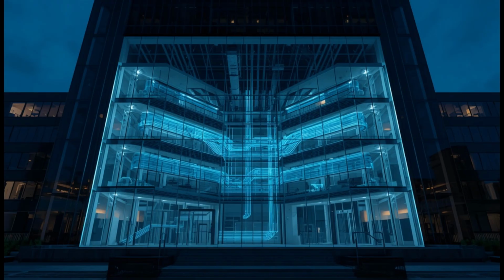Once set, a balancing damper rarely moves again, remaining fixed in that same careful position for years. A quiet, permanent correction, ensuring that a room near the beginning of the duct run receives no more air than a room much farther along it, despite one lying so much closer to the fan than the other. There is something almost old-fashioned about this particular piece of the system. A single mechanical adjustment made once, by hand, at the very beginning of a building's life, and then trusted to hold true for decades afterward, quietly outlasting nearly every occupant who will ever work beneath it.